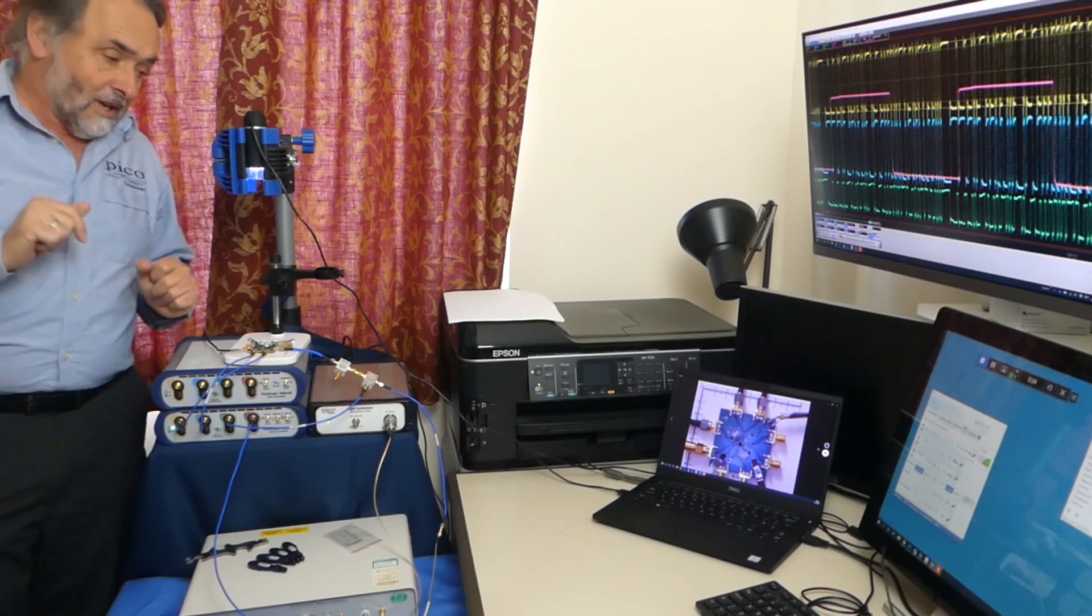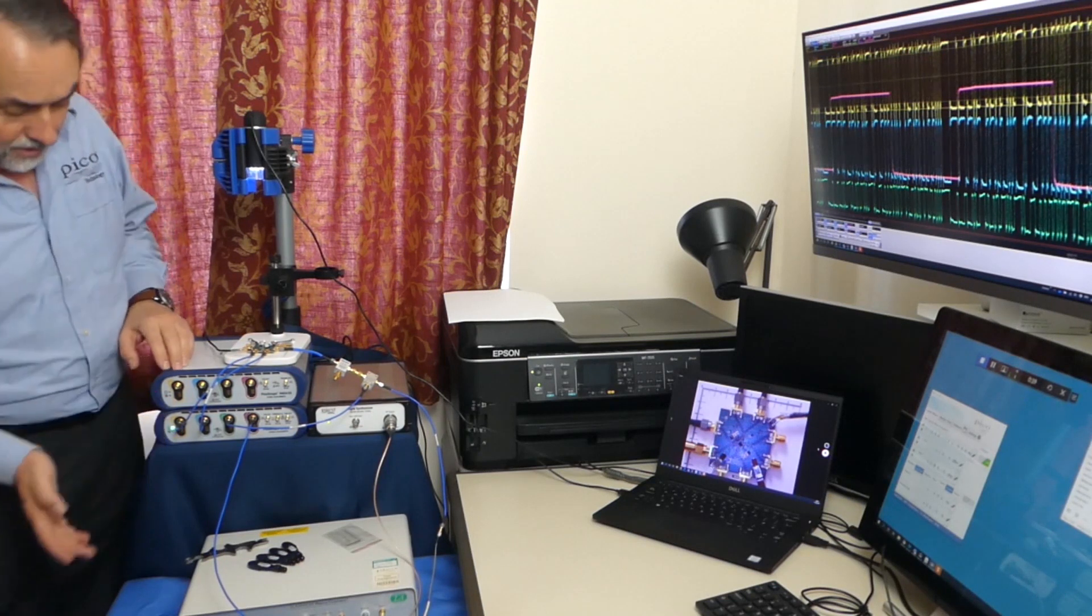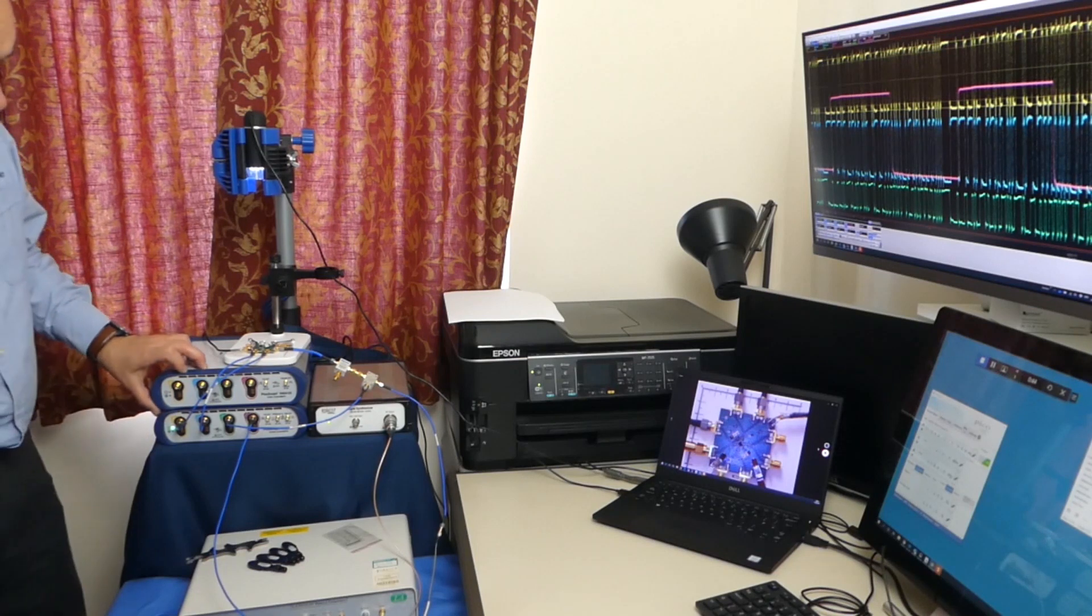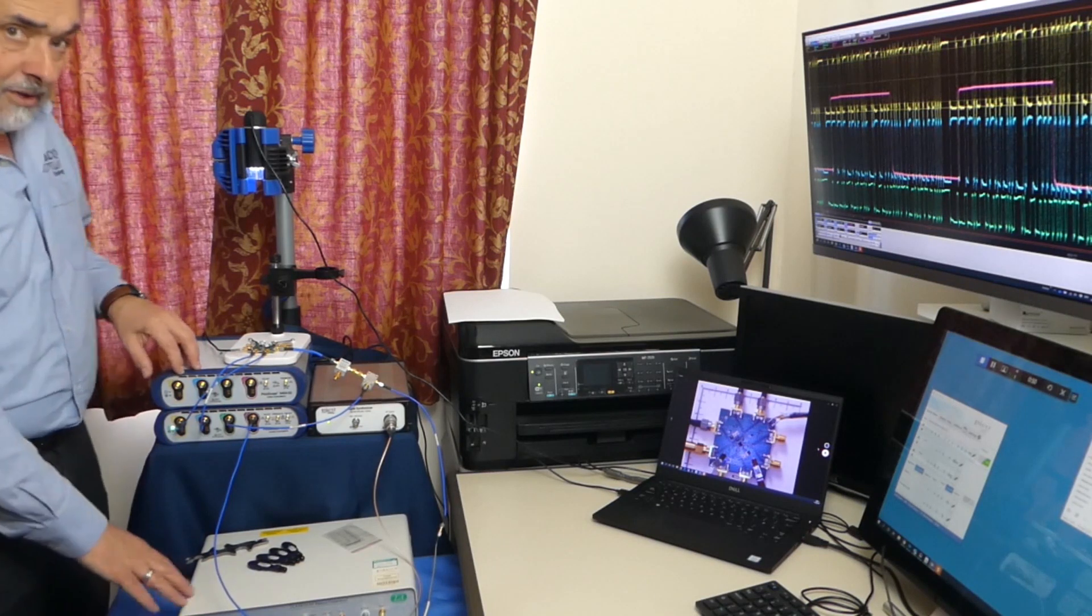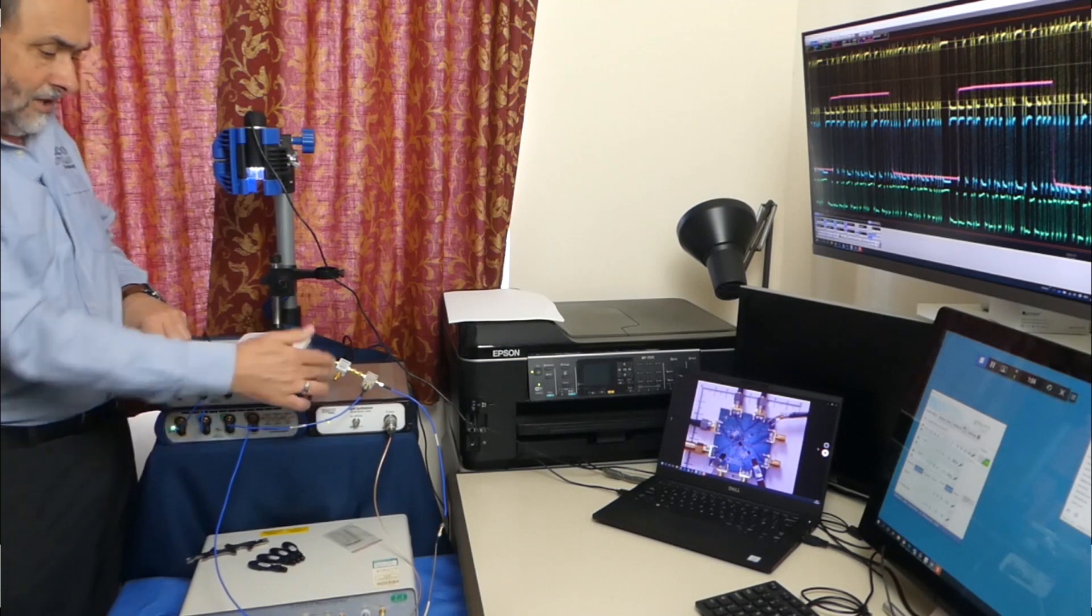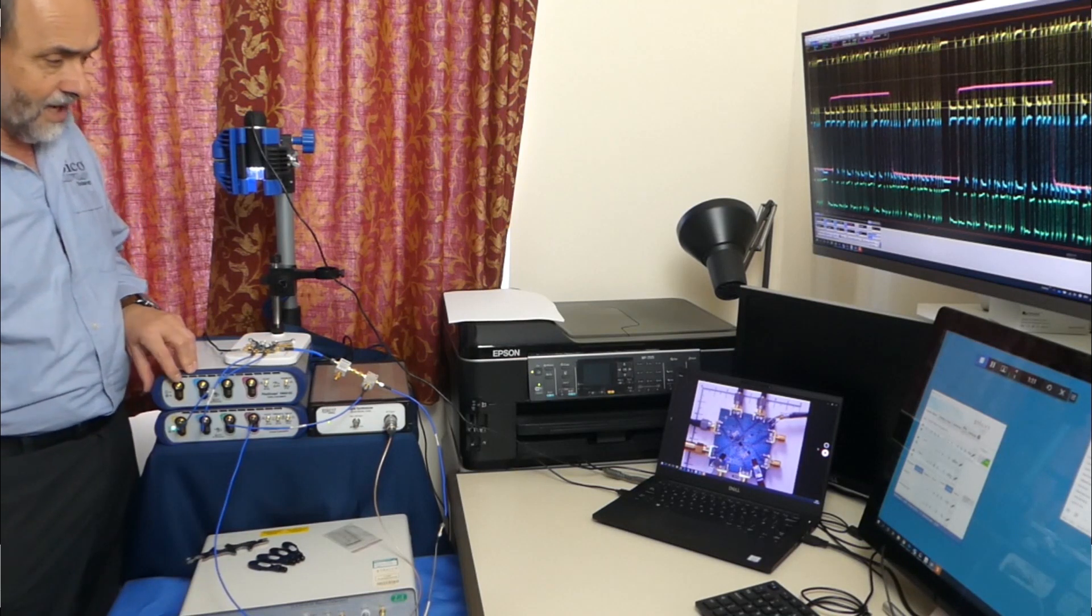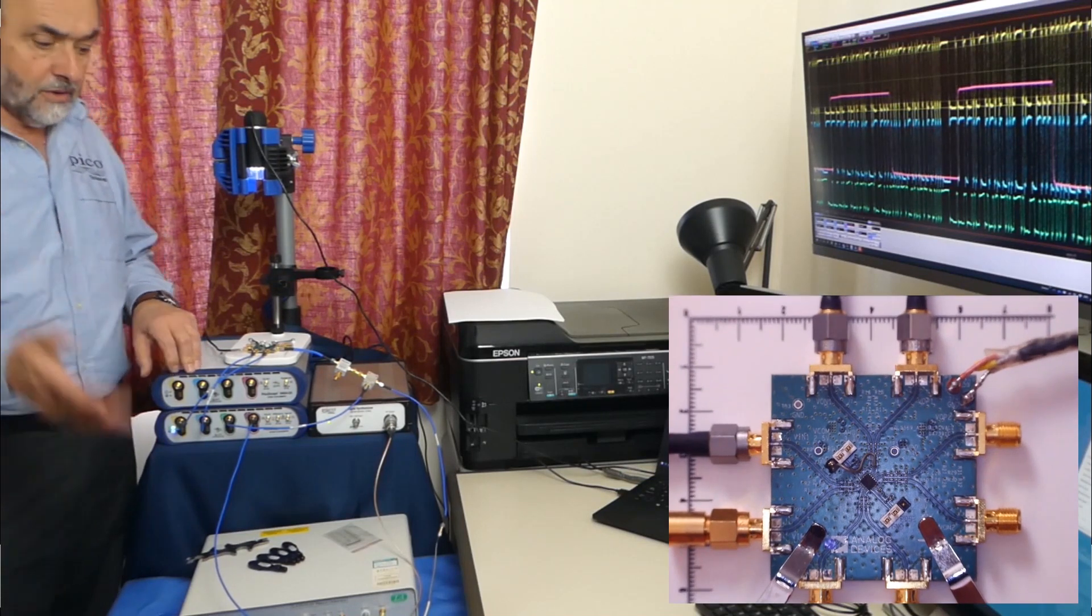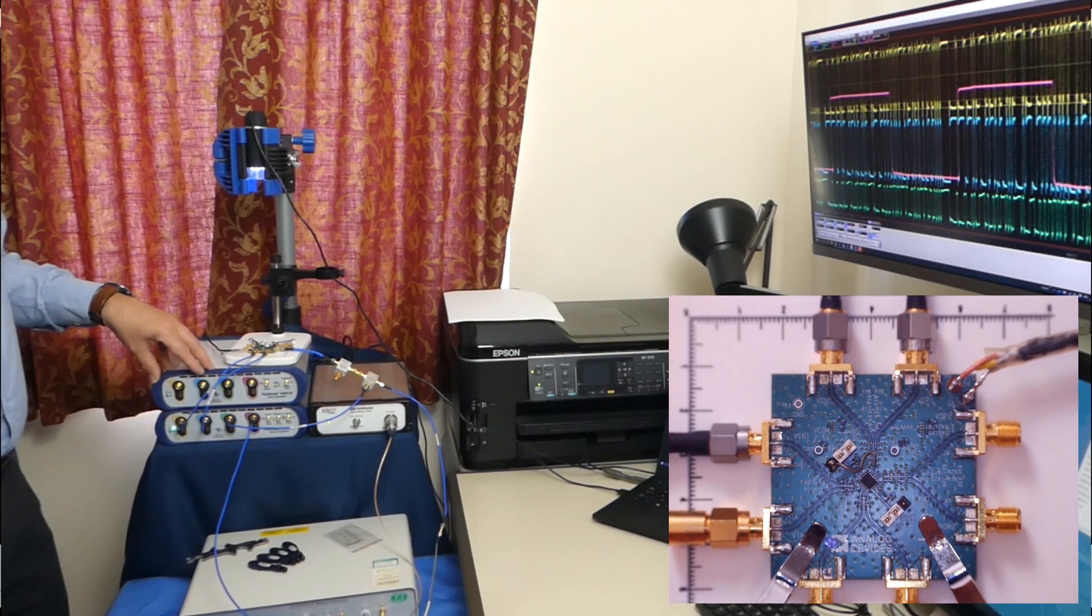Anyway, here we are. I've got two 9400s here - a four channel 16 gigahertz unit on the bottom and five gigahertz on the top. This is a PRBS generator, an old one, but bear with me on that. I'm clocking the PRBS generator from our agile synthesizer, the AS108, clocking it at 1.25 gigahertz, producing a PRBS stream at 1.25 gigabits per second.